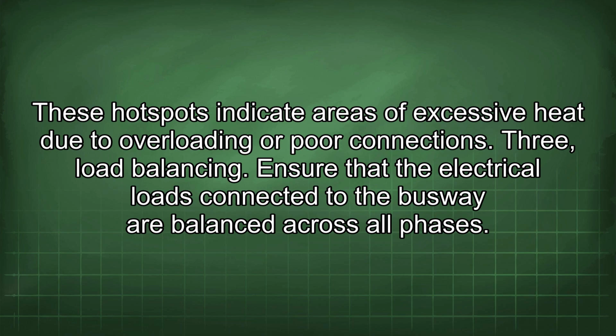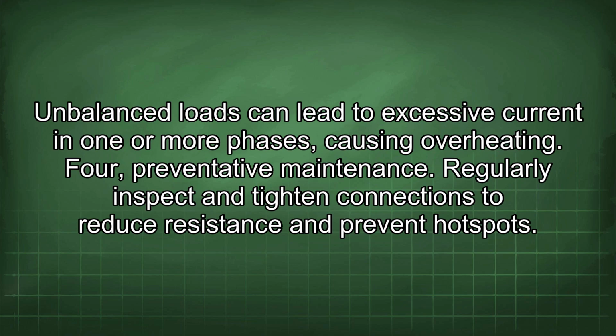These hotspots indicate areas of excessive heat due to overloading or poor connections. 3. Load balancing. Ensure that the electrical loads connected to the busway are balanced across all phases. Unbalanced loads can lead to excessive current in one or more phases, causing overheating. 4. Preventative maintenance. Regularly inspect and tighten connections to reduce resistance and prevent hotspots.